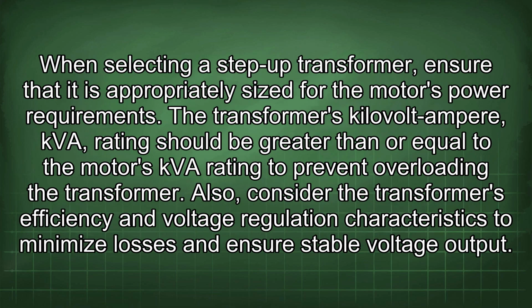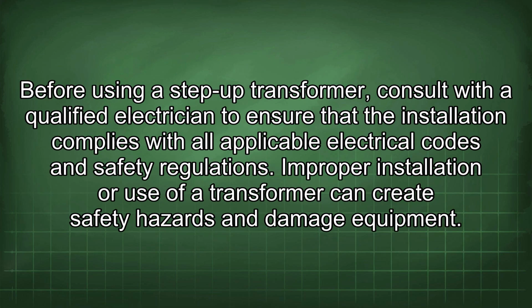When selecting a step-up transformer, ensure that it is appropriately sized for the motor's power requirements. The transformer's kilovolt-ampere (kVA) rating should be greater than or equal to the motor's kVA rating to prevent overloading the transformer. Also, consider the transformer's efficiency and voltage regulation characteristics to minimize losses and ensure stable voltage output. Before using a step-up transformer, consult with a qualified electrician to ensure that the installation complies with all applicable electrical codes and safety regulations. Improper installation or use of a transformer can create safety hazards and damage equipment.